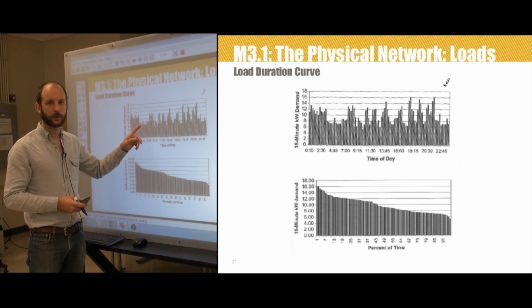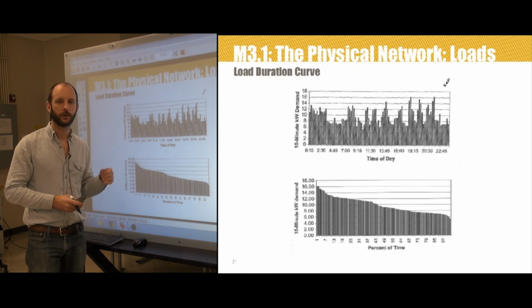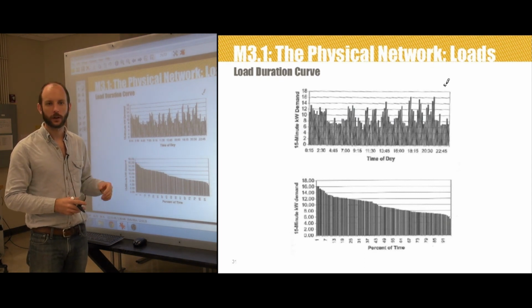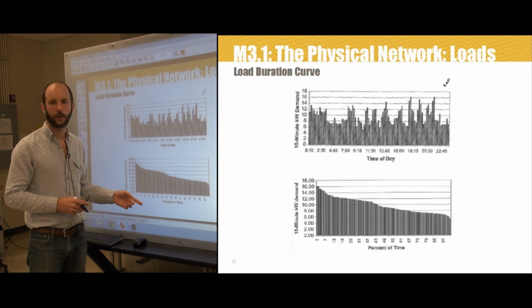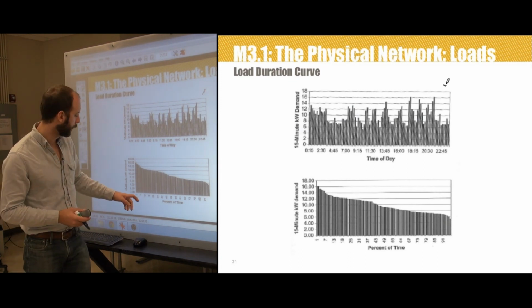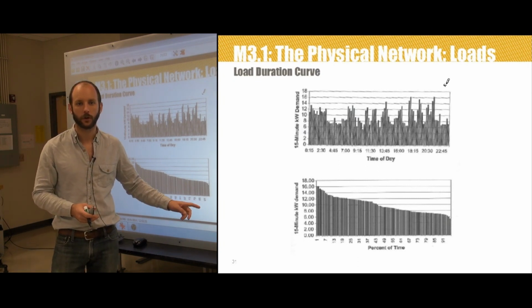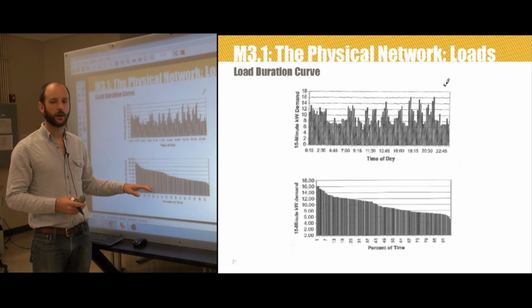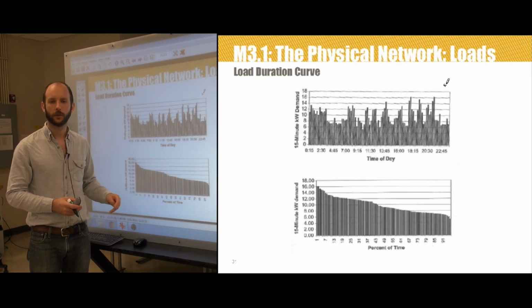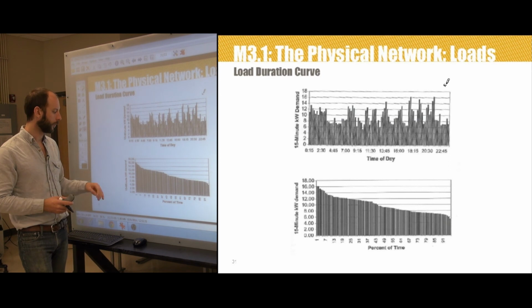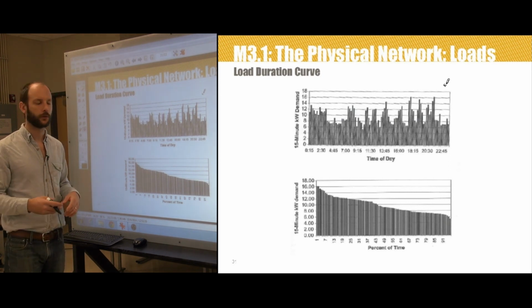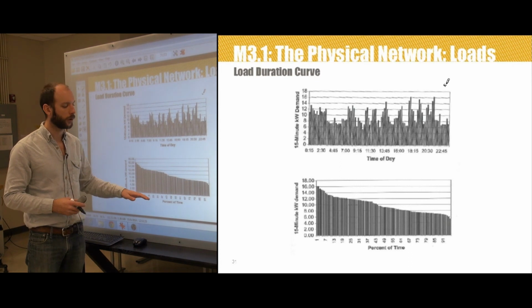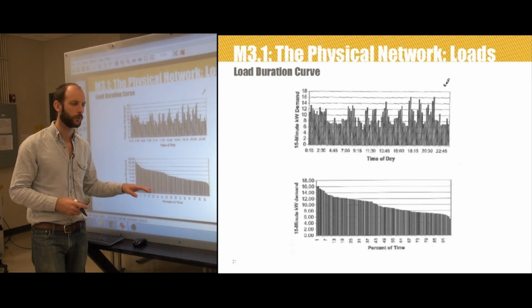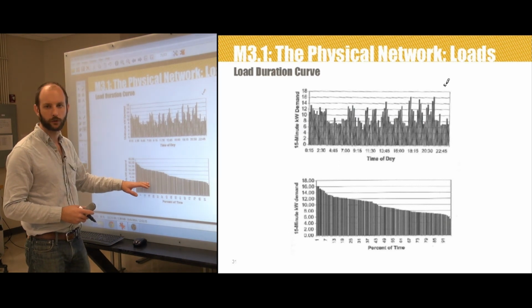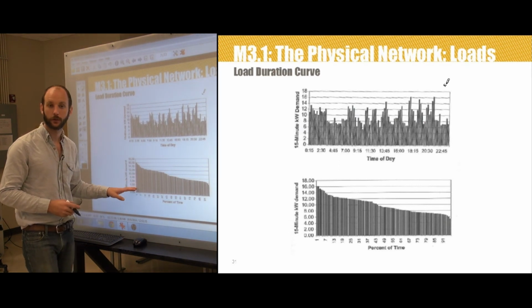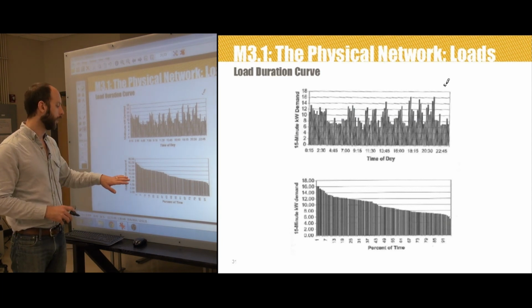We can also plot a load duration curve for diversified demand, similar to what we did previously for the aggregate load, right? Typically, a load curve is going to plot these 15-minute kilowatt demands versus, again, the percentage of time that the loading occurred over. And really what this is used for with transformers is to determine whether a transformer needs to be replaced due to an overloading condition, right? A transformer will be able to serve a certain amount of power. And you want to know how close to that operating limit, what percentage of the time, you are really operating near that limit. So these charts are very commonly used by distribution planners to determine whether or not they need to increase or add new transformers.